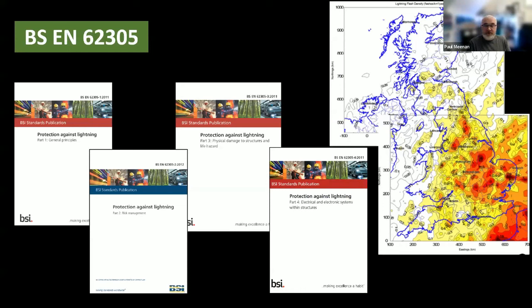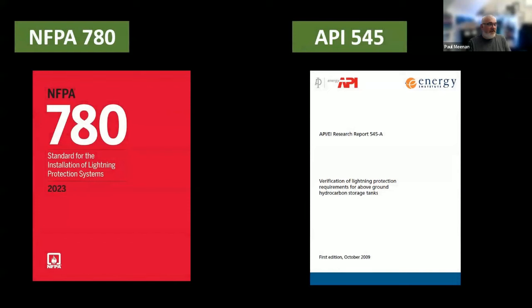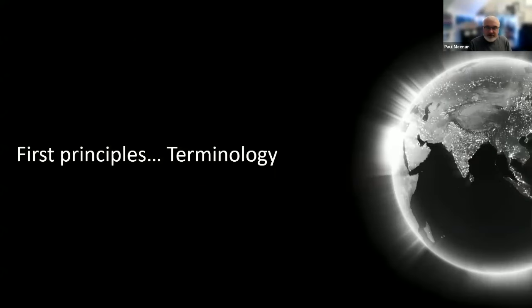It does need an update, in my opinion, and it probably needs an additional part as well for testing. So it could be a part five. Just again, my opinion, it would be great to see a standard on testing of lightning protection so that we can harmonize that a little bit better. Again, further afield, for lightning protection, NFPA published 780 again this year, the standard for installation of lightning protection. And there are also some secondary research documents, such as API 545 from the Energy Institute, on verification of lightning protection in specialist areas. There are lots and lots of standards.